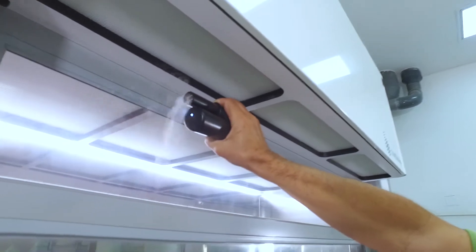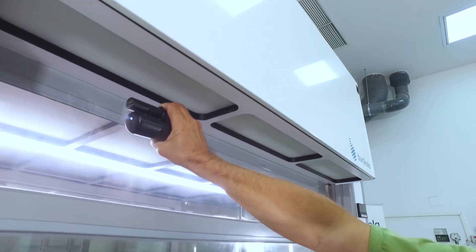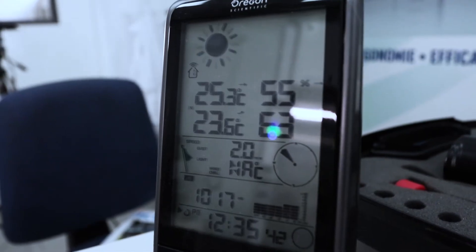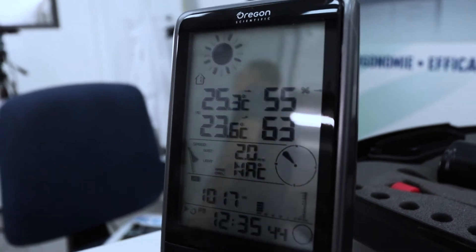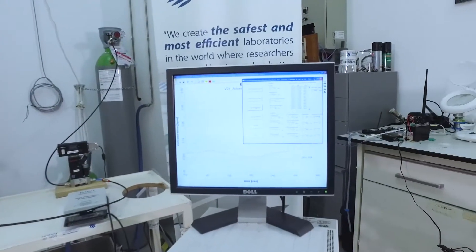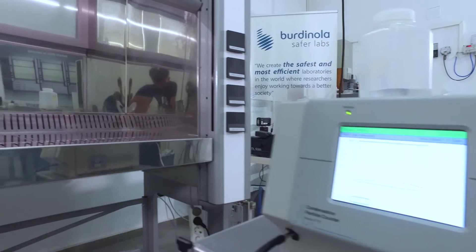The design is evaluated through tests carried out in a room conditioned specifically for the purpose, with controlled conditions of temperature, air humidity, and air velocity that allow the results to be repeatable and comparable.